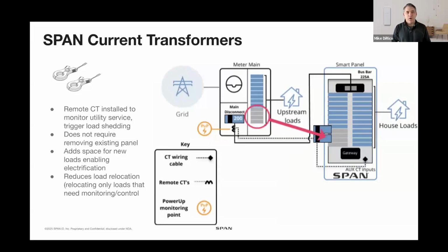We talked a little bit about SPAN 24 and using it as a sub panel. One really important accessory to add when using SPAN 24 as a sub panel is our current transformers. What our CTs allow is for all the PowerUp software I talked about to run - particularly on grid, you're going to want to know how much total draw you're using. If SPAN is a sub panel, we don't know the draw unless we have CTs, and wouldn't know how much power is being utilized by the main panel. So the CTs let us monitor entire home usage as well as understand what the SPAN panel is using and potentially make adjustments, like ramping down the EV charger a little to keep you in the safe zone for available home capacity.